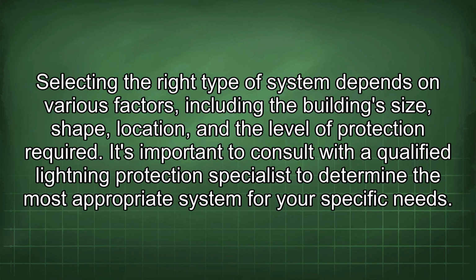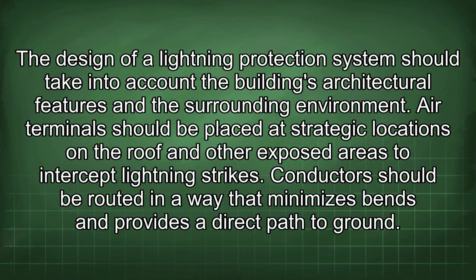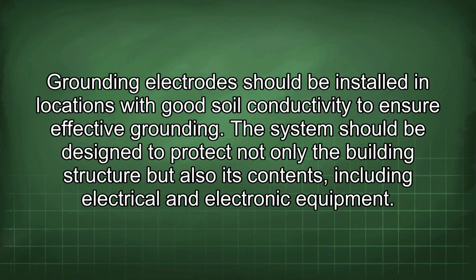Selecting the right type of system depends on various factors, including the building's size, shape, location, and the level of protection required. It's important to consult with a qualified lightning protection specialist to determine the most appropriate system for your specific needs. The design of a lightning protection system should take into account the building's architectural features and the surrounding environment. Air terminals should be placed at strategic locations on the roof and other exposed areas to intercept lightning strikes. Conductors should be routed in a way that minimizes bends and provides a direct path to ground. Grounding electrodes should be installed in locations with good soil conductivity to ensure effective grounding.